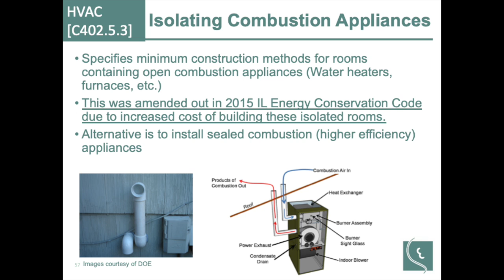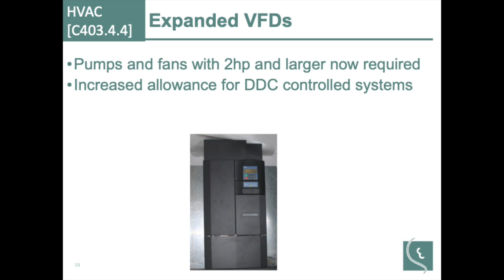VFDs - this threshold has moved down. It used to be between 5 and 7.5 horsepower. Now it's down to 2 horsepower, and larger motors are required. There is an allowance if you have DDC controlled systems that lets that threshold go up some. I have the reference up here called out as far as what the section number is.